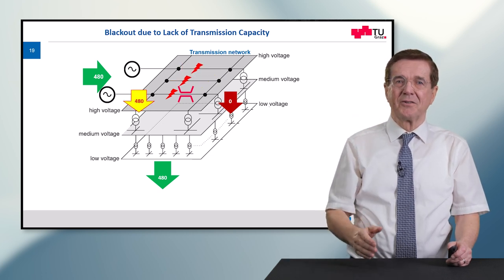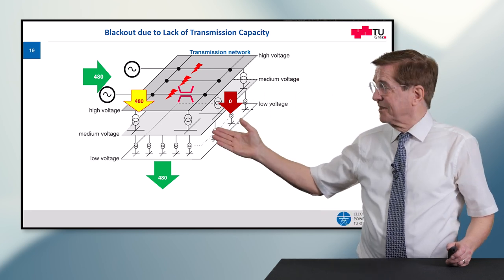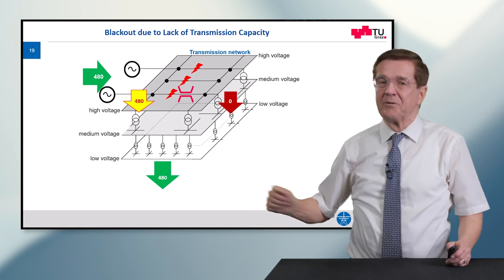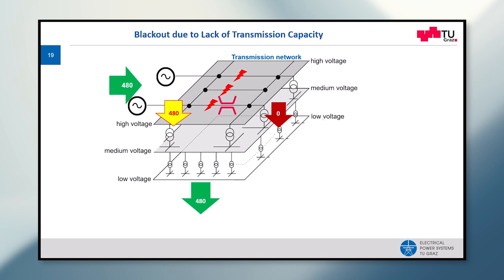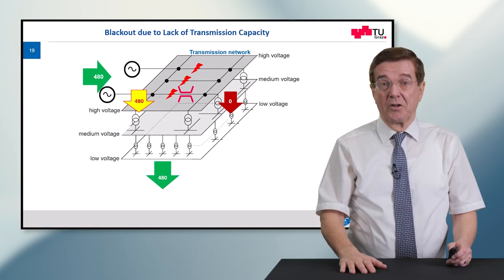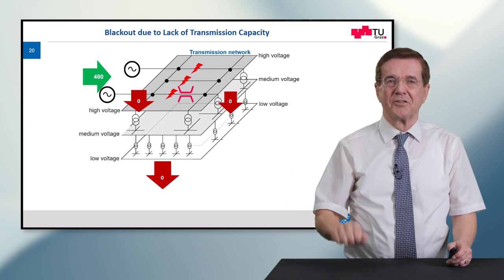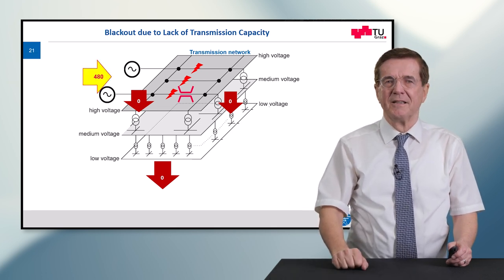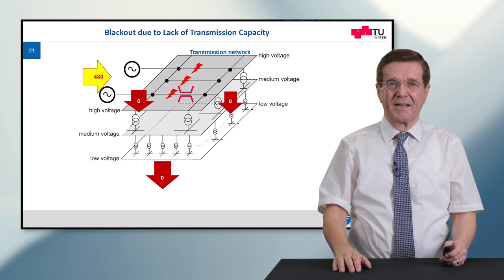First line number two, then line number three — this means the right side of the transmission network is no longer able to bring energy down to the customers. At the same moment the energy flow is transferred to the left side, which as you can see goes into overload and will also trip out. This means the consumers have no energy at all anymore, and most likely the power plants will also run into problems due to the sudden deloading of their turbines.